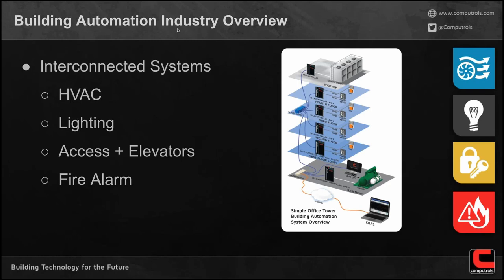An input is something we read into the system, like a temperature sensor, a humidity sensor, or a daylight sensor. An output is a device used to control a piece of equipment. For instance, in a daylight scenario, we could have a sensor that monitors daylight, so it knows when the sun is up and down. We may have an output device, a relay, used to turn lights on and off - very similar to a light switch, but an automated one, controlling the lights.